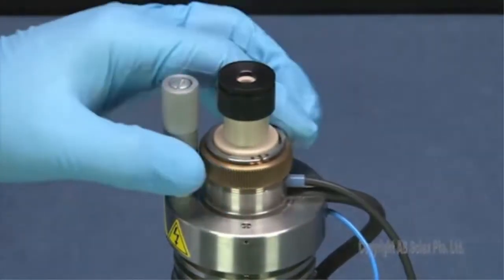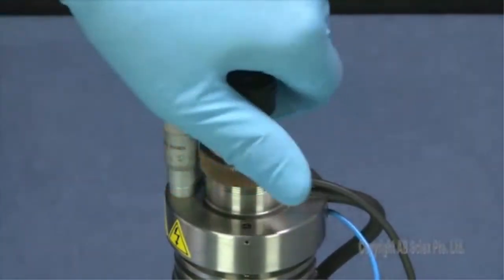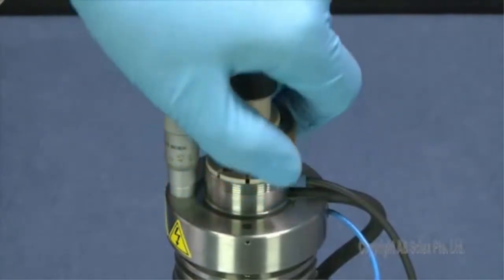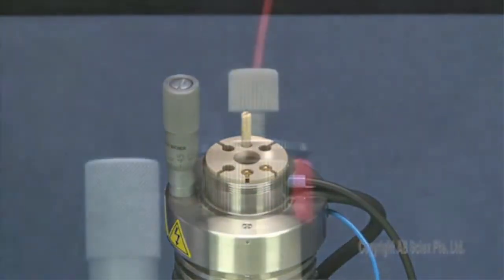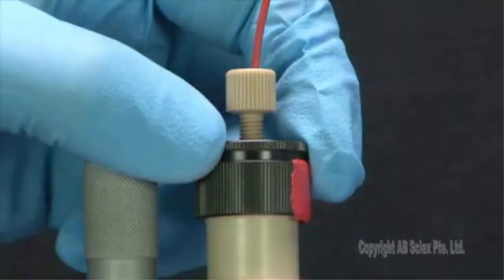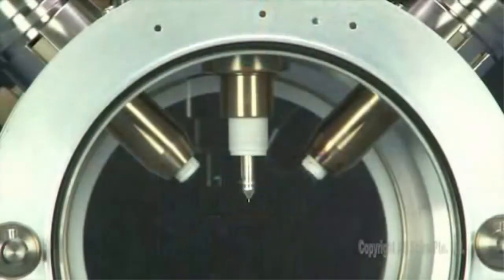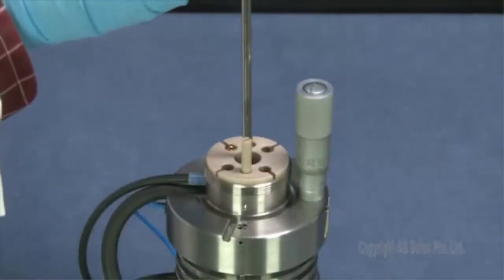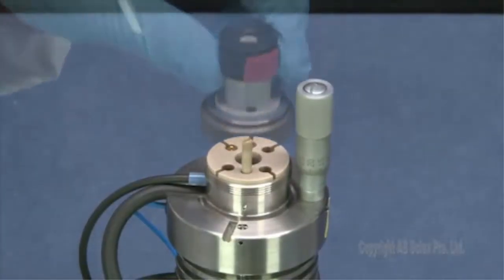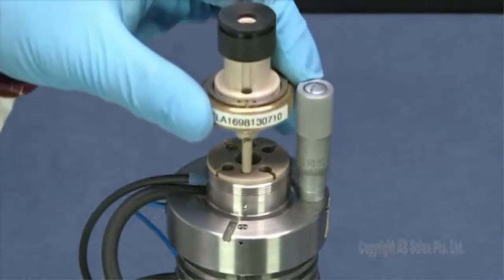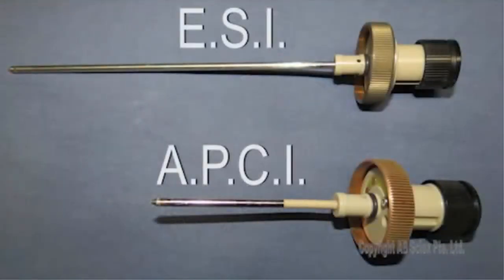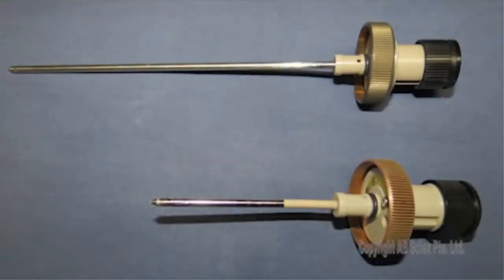Gently pull the probe straight up out of the tower. Do not let the tip of the probe touch anything as you remove it or store it. The tip can be retracted using the black adjustment nut to protect it from damage during probe replacement. Depending on your needs, the new probe may be the same type or a different type probe, i.e. from the ESI to APCI.